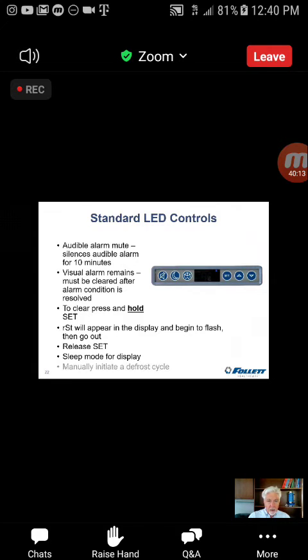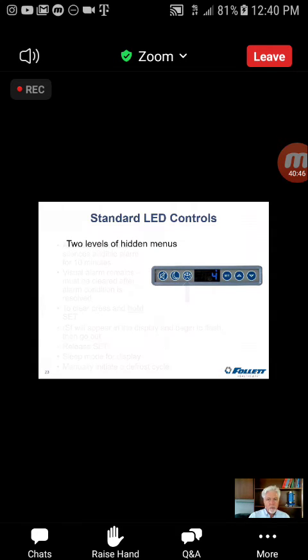And then finally, for the freezers, this is mainly a service tool. You can manually initiate a defrost. This is mainly so that if you're running diagnostics on a unit, and you want to check the defrost cycle, you want to check the defrost heaters, make sure it's doing what it's supposed to be doing, rather than waiting hours for the next defrost cycle to occur under the regular time sequence, you can manually initiate a defrost by touching that, holding it several seconds, and the unit will go into its defrost cycle. So it speeds up the troubleshooting process. So it's really a service tool.